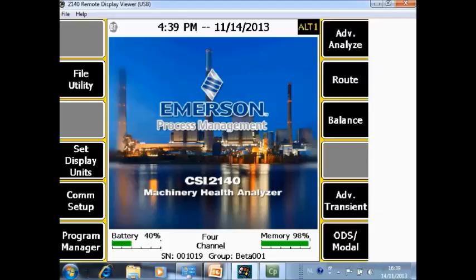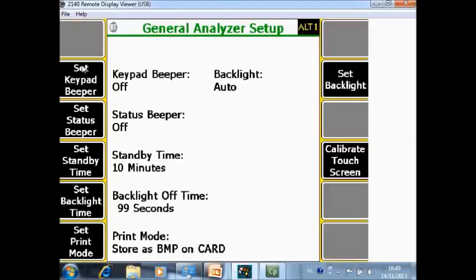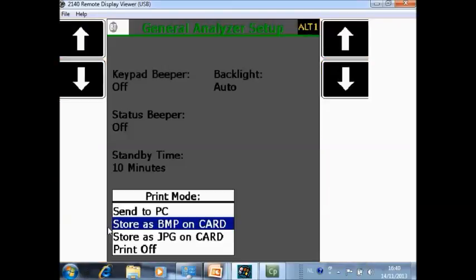What you're seeing now in front of you is the home screen of the CSI 2140 machinery health analyzer. There are several options for print functions, but let's start with the beginning. When you're in the home screen, the first thing to verify is go to Alt 2, go to General Setup, and here F6 set print mode. You can specify that if you do a print action on the CSI 2140, if you want to send it to the PC, store it as a bitmap on your memory card inside the analyzer, store it as a JPEG on the memory card in the analyzer, or disable this feature.